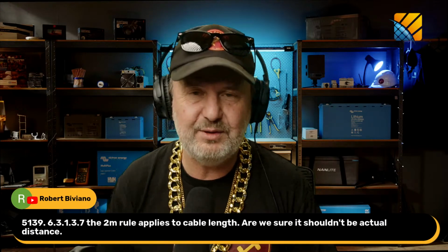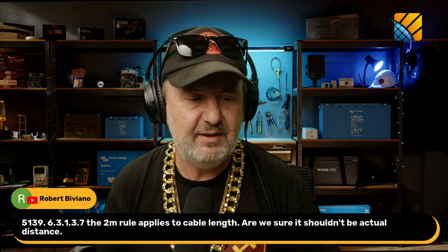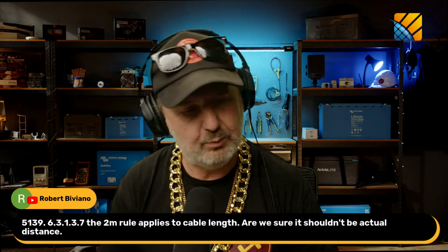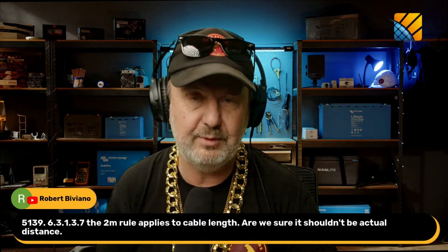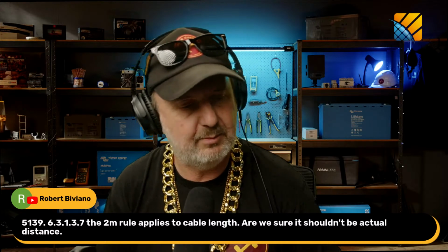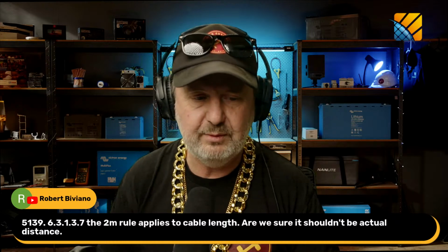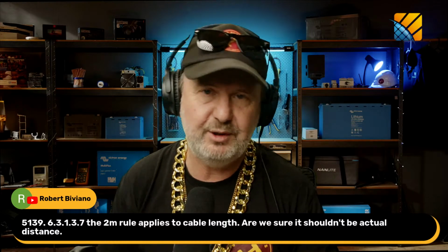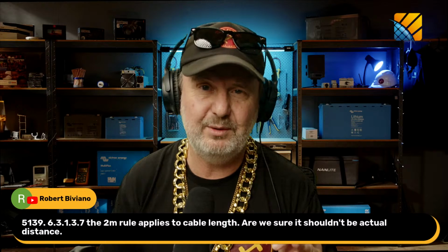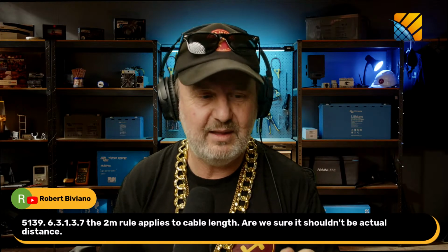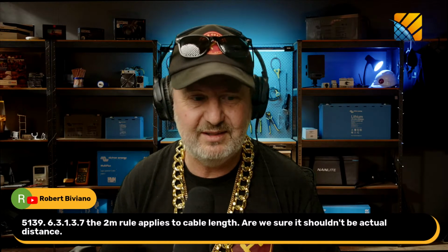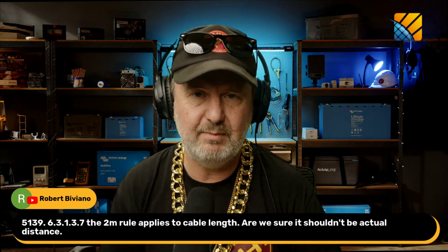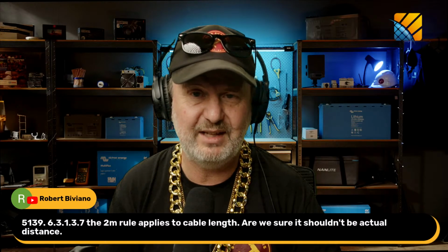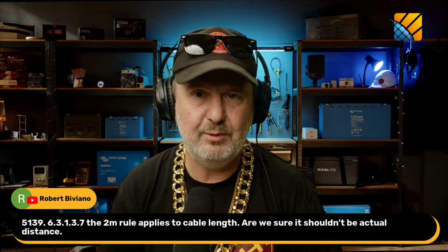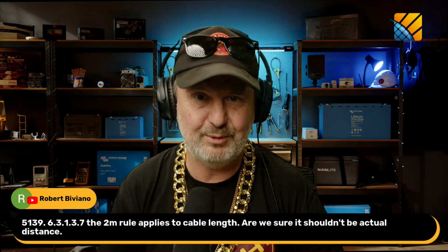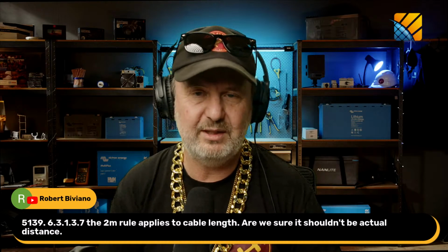Rob's referring to the new battery standard AS/NZS 5139, clause 6.3.1.3.7, which states there's a 2-meter rule for the length of cable from the output terminals of the battery system to its point of isolation. That's cable run, not just physical distance. Basically, you're trying to reduce as much as possible the cable that's not overcurrent protected or isolated, so the 2-meter rule means you want it as close as practicable.